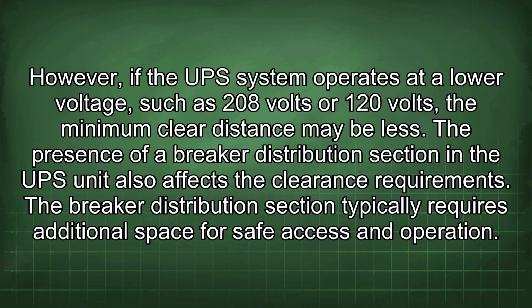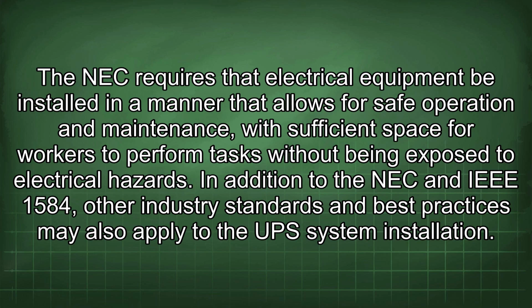However, if the UPS system operates at a lower voltage such as 208 volts or 120 volts, the minimum clear distance may be less. The presence of a breaker distribution section in the UPS unit also affects the clearance requirements. The breaker distribution section typically requires additional space for safe access and operation. The NEC requires that electrical equipment be installed in a manner that allows for safe operation and maintenance, with sufficient space for workers to perform tasks without being exposed to electrical hazards.